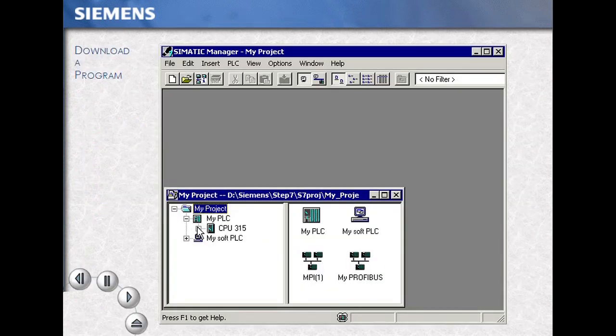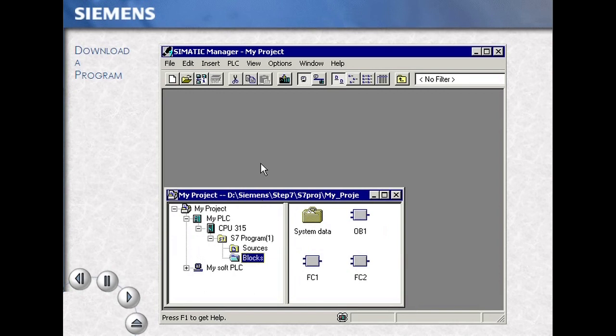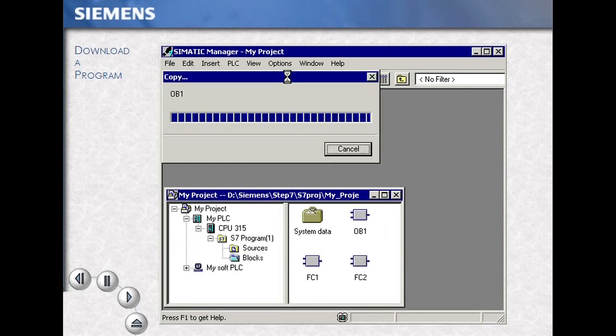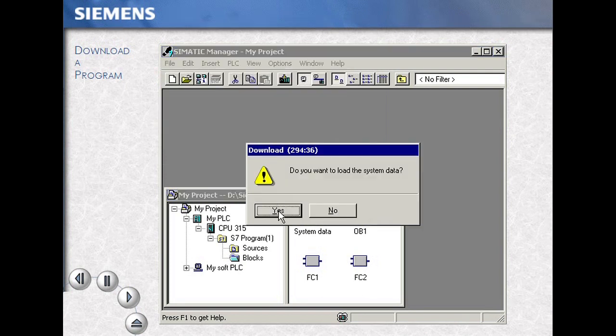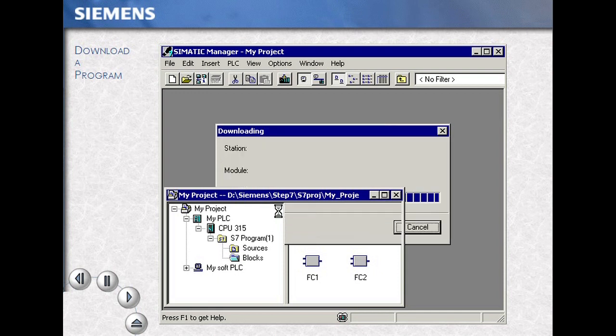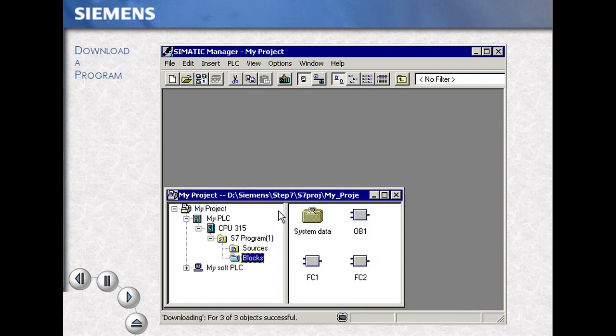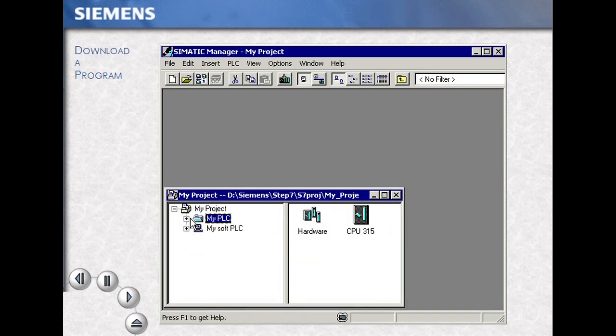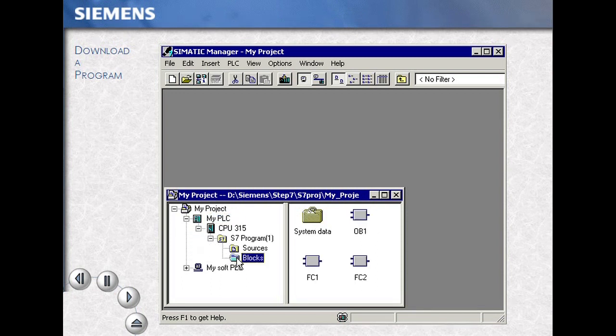This subroutine will then become simply another element within our program catalog. Open your project and your program to the blocks folder. Highlighting the blocks folder and using the download icon downloads the entire program. If you answer yes to load the system data, you also download the hardware configuration for your station. You can selectively make downloads of individual code blocks by opening your program folder to the blocks folder, then selecting only the block or blocks you choose to download.